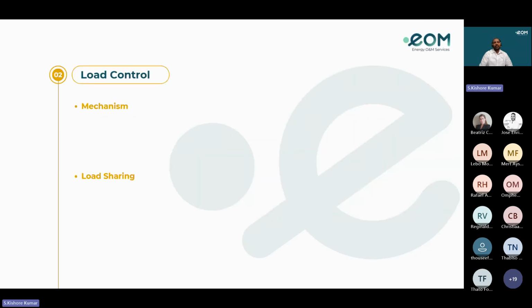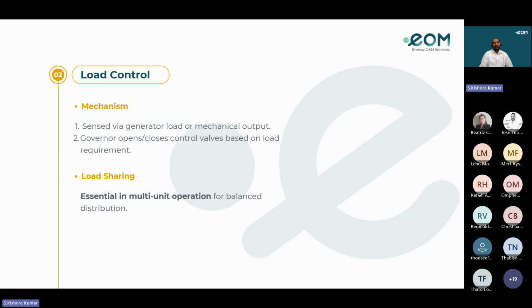Load control. What is load control and what is the objective? Our objective is to adjust the steam flow to match power output with load demand. Mechanism: the load is sensed via the generator or mechanical output, and the governor opens or closes control valves based on the load requirement. Load sharing is essential in multi-unit operation for balanced distribution.